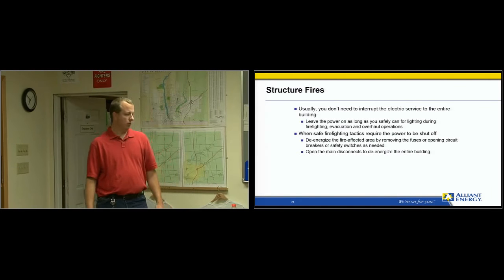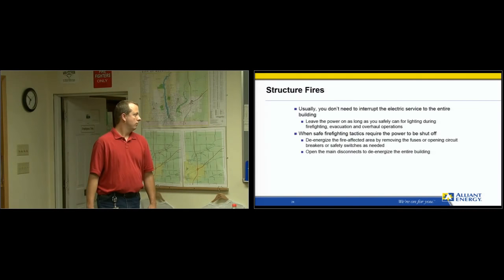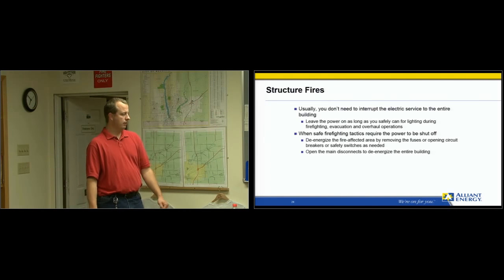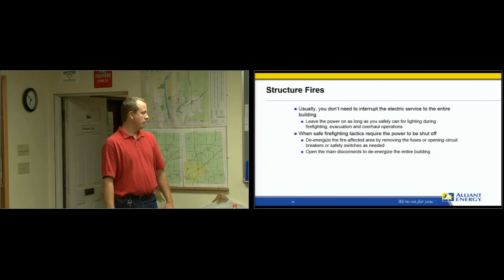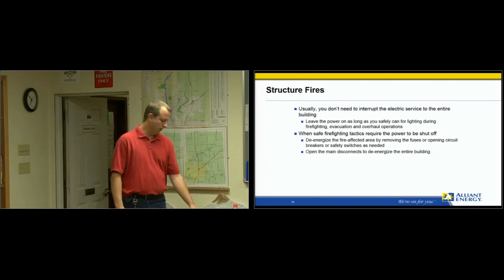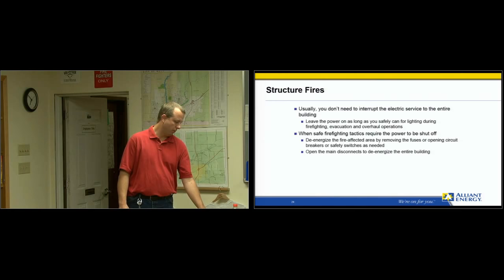You guys know this, but if we've got a fire we interrupt the service. If it can't be re-energized that night, or we need an inspector to take a look, we'll wait till morning, let someone inspect it before re-energizing, or gut the panel out, or do whatever's needed so they can start drying it out if they're going to try to rehab it.